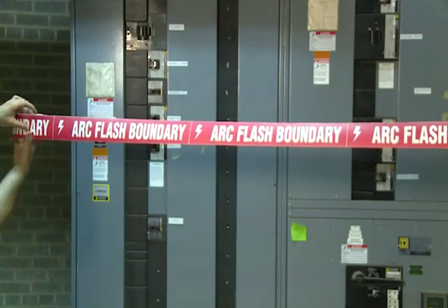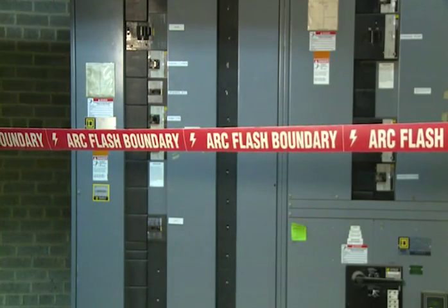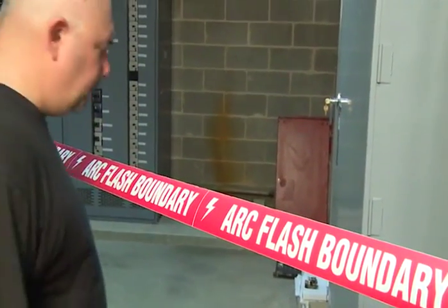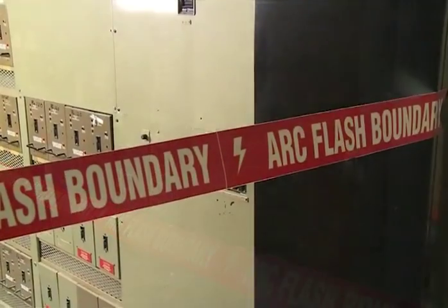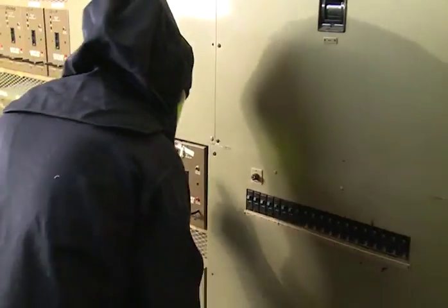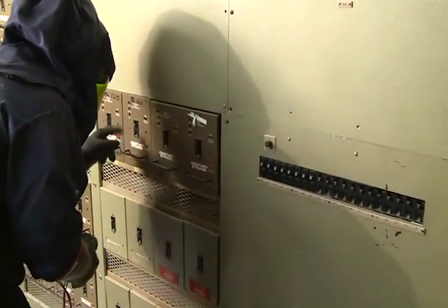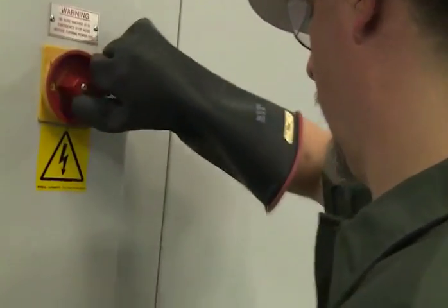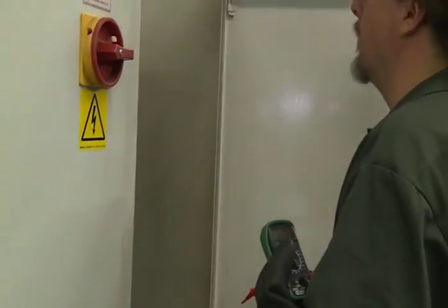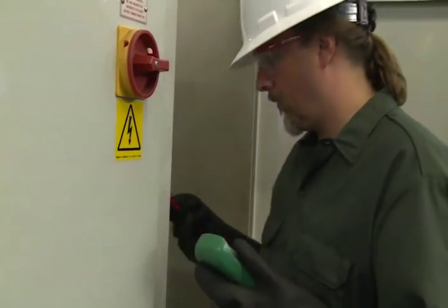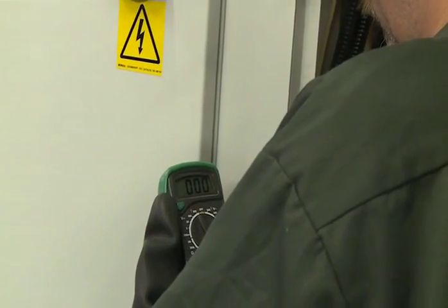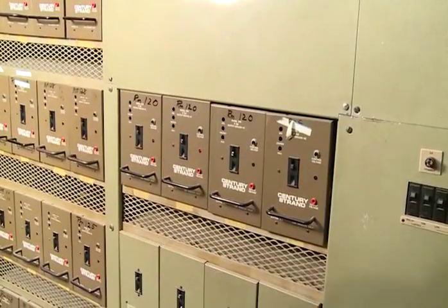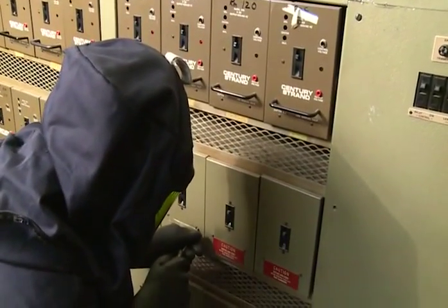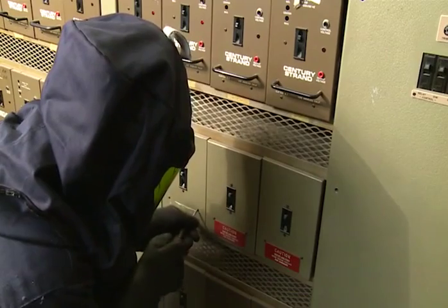The boundary must be clearly labeled and must physically restrict access to the area. Unqualified electrical service personnel and other workers may not cross the arc flash boundary. Even qualified electrical workers can't cross the boundary unless they are wearing appropriate protective clothing and PPE with the right arc rating. Once these precautions have been taken, the equipment can be tested. Only when it is verified that the power is off does an electrically safe working condition exist. That's when actual maintenance or repair of the equipment can begin, without any risk of arc flash or electric shock.